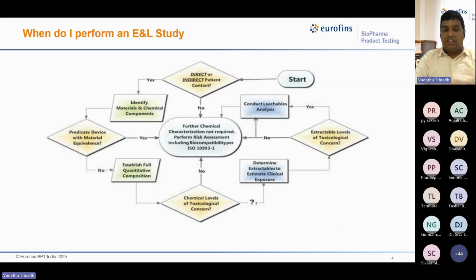Whereas if any chemical levels are above toxic levels, then we have to do an extra study for the specific medical device at clinical exposure to find out which materials are above the toxic concerns. Still, if there are no chemicals above toxic concerns, again, there is no requirement for chemical characterization. Directly, you can proceed to the risk assessment. Whereas, if anything is found above the toxic concerns, then again, a leachable study needs to be performed.